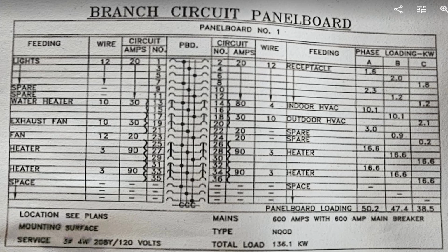For this same project, I have my panel schedule. Circuit A is going to be right here on number 1. So that lighting circuit we were looking at is right here on number 1, circuit number 1. So I know that it's a 20 amp circuit. In my estimating, when I'm calculating my breaker, I'm going to write that down. I need a 20 amp bolt-in for this. I'm going to have 12 gauge wire. It's calling out 12 gauge wire. I calculate all my time and I look through it.